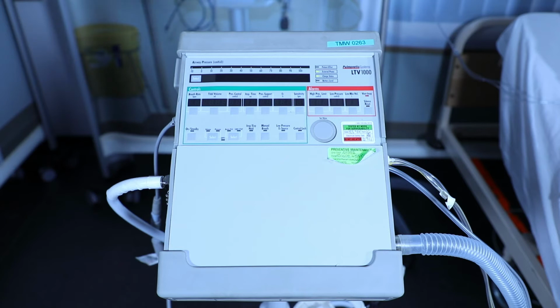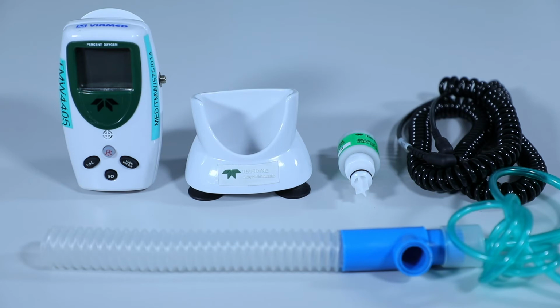Something that we've also not discussed for this ventilator is that it has no internal O2 analyzer. So to combat that, and in order for us to be able to analyse the concentration of oxygen that we've actually set and confirm that it's been delivered, we have to use an oxygen analyzer and connect it up to the LTV. We use the Teledyne O2 analyzer, which there is a separate video on, so this won't go into how to operate it, but what we will do is discuss where it goes in relation to the ventilator.